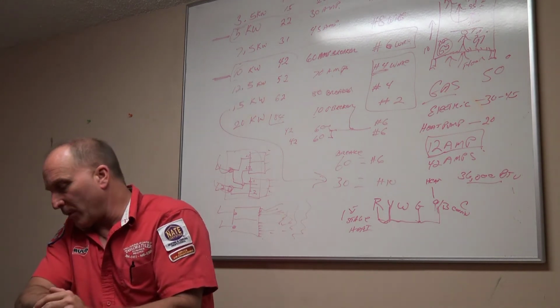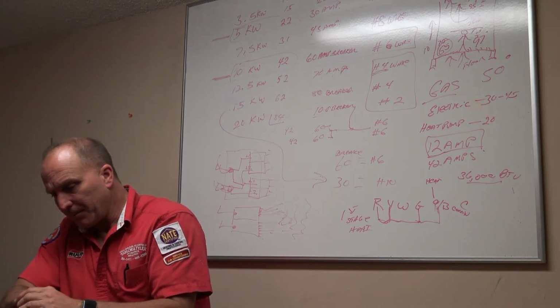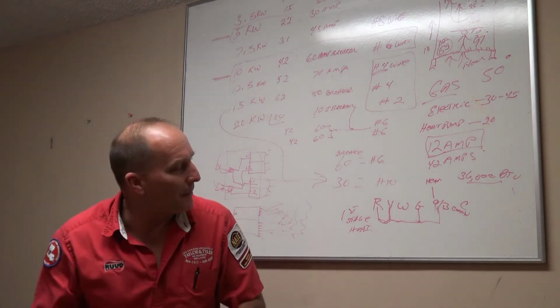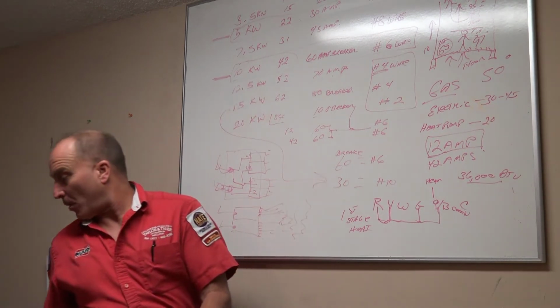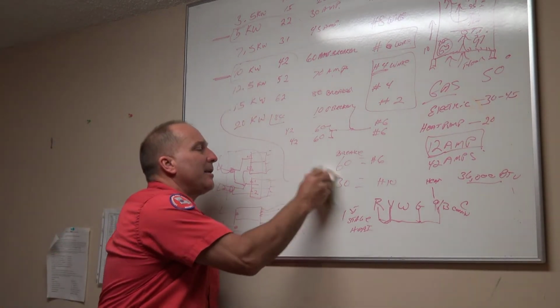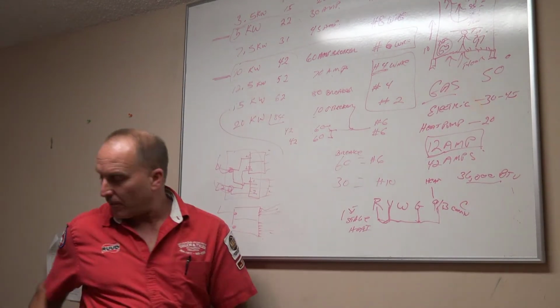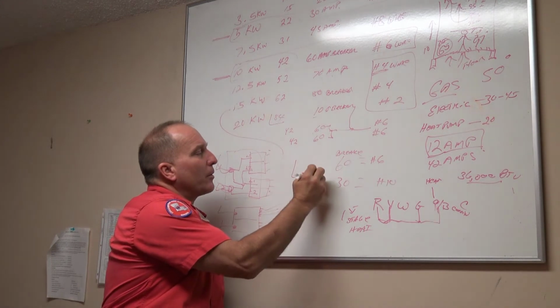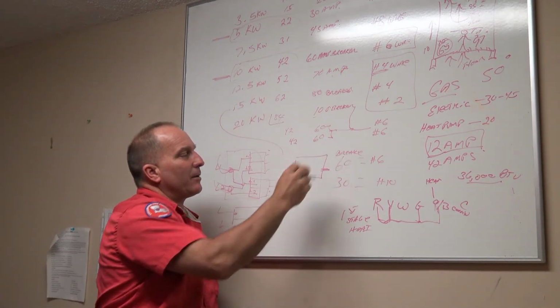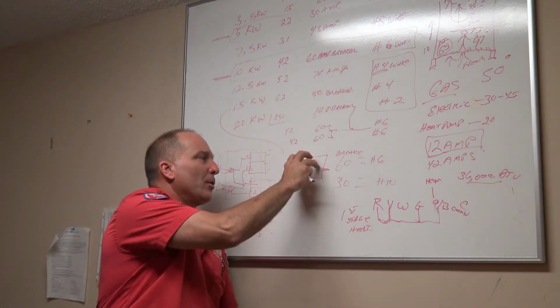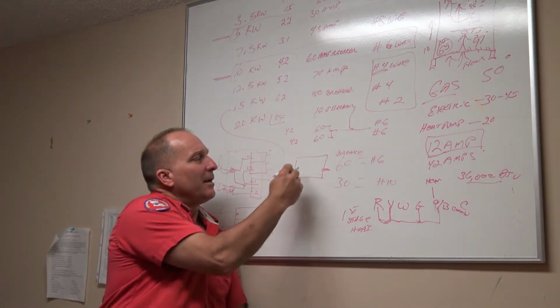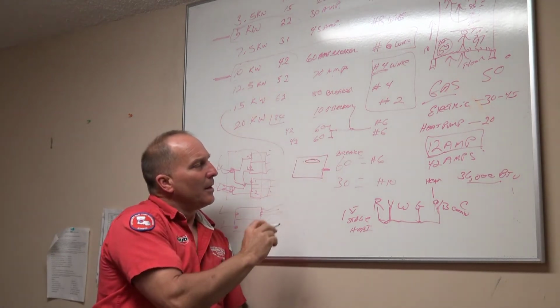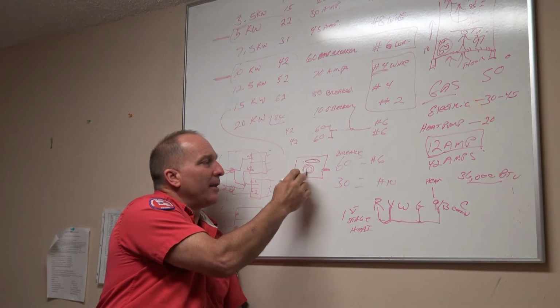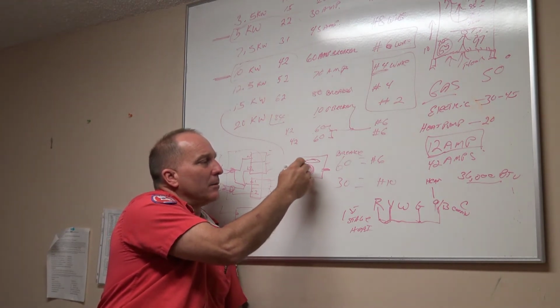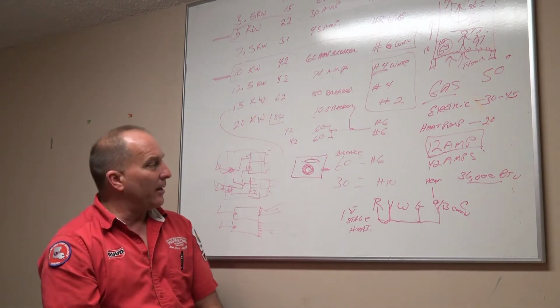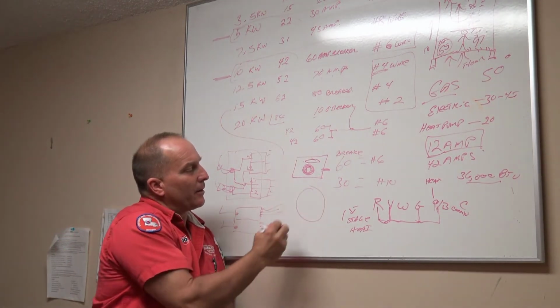A heat anticipator, for those of you who haven't watched the gas furnace video, is found in an old manual thermostat with the mercury bulb on it. And that old thermostat has a heat anticipator in the inside or the front part of it. So here's your old mercury bulb thermostat with a little lever on it, and you move it up and down to change the temperature. You pull the cover of that thermostat off, and you will see inside a little mercury bulb up at the top, and it's got what's called a helix coil. Then inside there they got a little round disc, and I'm going to make that disc bigger.